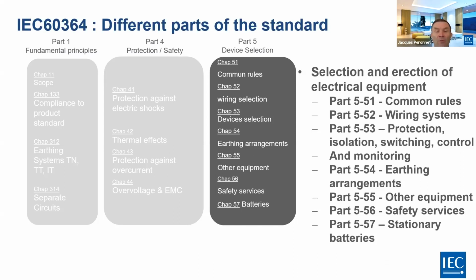The chapter 56 is everything regarding safety services. So this is more or less all the services you have to deliver when you have an outage in the building and you need, for example, to evacuate. So you have to make sure that all the signs that you have and the way to evacuate are correctly fed during this lack of services in the building. And then there is a new chapter which is not published yet, but is going to be published normally at the beginning of next year. It's about stationary batteries.